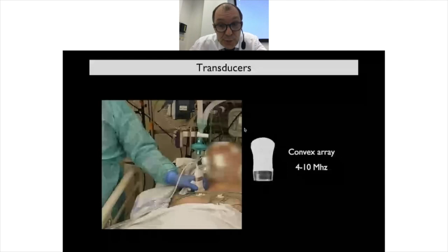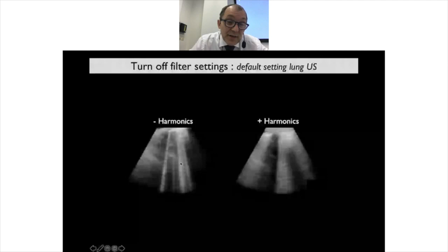Maybe the most important thing when you use an ultrasound machine to perform lung ultrasound is that you have a dedicated default setting for lung ultrasound. You need to turn off all filters, because the most important principle in lung ultrasound is you want to see artifacts. Artifacts arising from the pleural line. And if you use these filters, harmonics, etc., it will blur. It's designed to get rid of all these artifacts. And so it blurs the artifact. So you need to turn off these filters. And then when turning off these filters, you can see much better these clear artifacts. So this is maybe the most important thing to remember: turn off the filters.